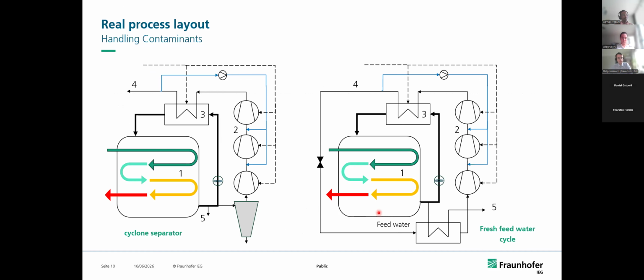Here on the left doesn't change much, but we just apply a cyclone separator. Particles and dirt would come off here, and a cleaner superheated steam mass flow could be sucked into the compressors. But this is not 100% safe, of course, because we still have the open loop system. Here, this could be an alternative cycle.